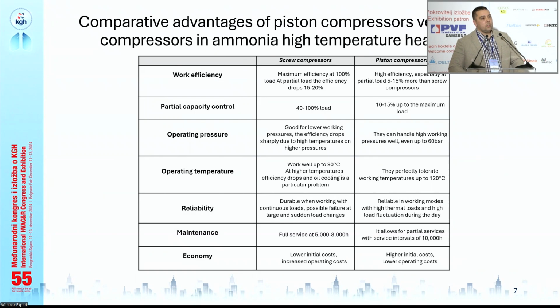Also, piston compressors behave better on higher pressures and temperatures. We know that we have problem with the oil cooling on the higher temperatures with screw compressors. From the reliability and the maintenance point, what is the benefit with piston compressor is that we can target maintenance. We don't need to do overall maintenance, and service hours are a bit longer.